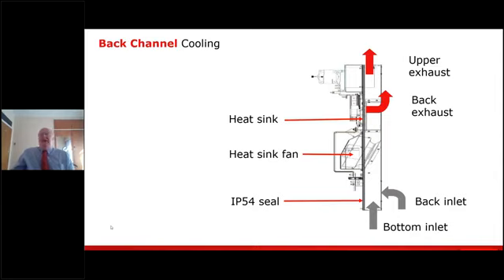Obviously, consideration has to be given to the outside air quality, but if it is suitable, using the heatsink cooling fans and appropriate mounting and ducting, the filtered external air at temperatures of up to 50 degrees centigrade can be used to exhaust approximately 85 to 90% of the heat loss from these VSDs directly back outside the switch room. And this is done without affecting the switch room pressurization. The switch room air conditioning system then only needs to be sized for the remaining 10 to 15% losses, which is actually going into the switch room. So utilizing this feature can dramatically reduce the air conditioning requirements of the switch rooms. This provides a significant project cost saving, along with operational ongoing cost savings, compared to VSDs that don't have such a design feature.